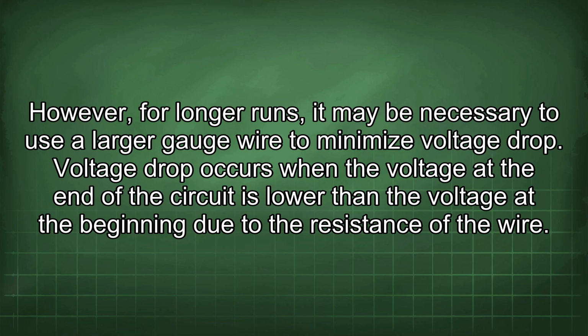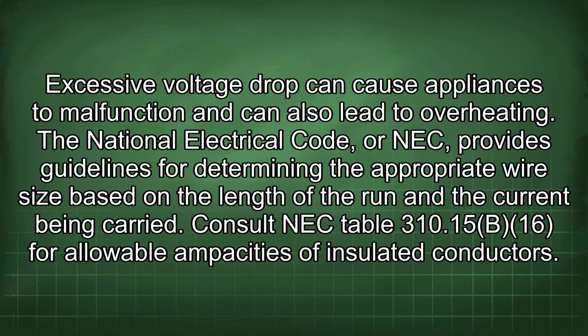Voltage drop occurs when the voltage at the end of the circuit is lower than the voltage at the beginning due to the resistance of the wire. Excessive voltage drop can cause appliances to malfunction and can also lead to overheating. The National Electrical Code, or NEC, provides guidelines for determining the appropriate wire size based on the length of the run and the current being carried. Consult NEC Table 310.15(B)(16) for allowable ampacities of insulated conductors.